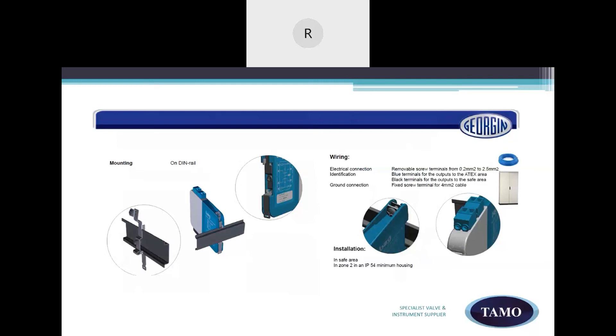Electrical connections have removable screw terminals, 0.2 mm2 to 2.5 mm2, color coded blue terminals for outputs to the ATEX area and black terminals for the outputs to the safe area. The ground connection is a fixed screw terminal for 4 mm2 cable. Just a reminder that the ground terminal must be connected to an equipotential ground network with a wire with 4 mm2 minimum wire selection.